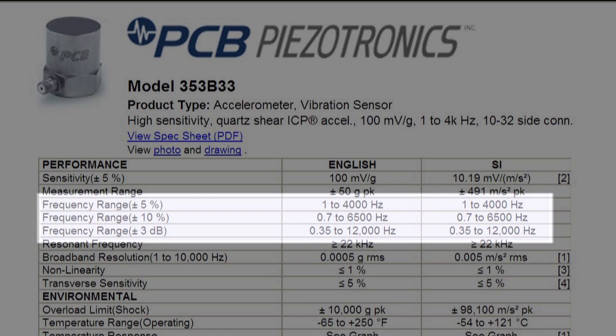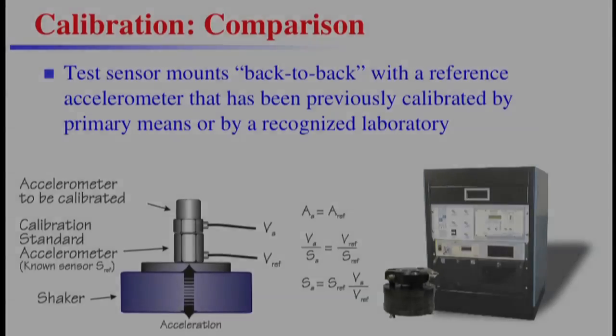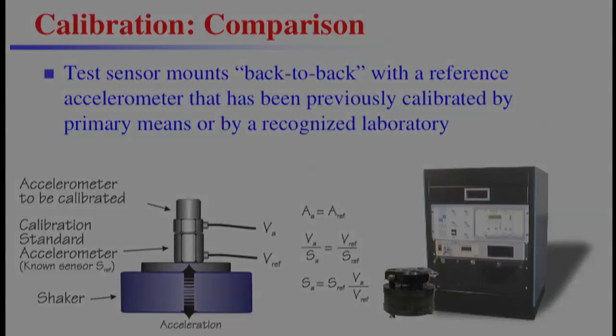The measured amplitude frequency response of a sensor is typically scaled in percent from the reference sensitivity. The comparison or back-to-back method is performed by mounting the sensor under test directly to the surface of the reference standard, which has a calibration traceable to one of the national labs. The fundamental assumption made is that the acceleration of the reference accelerometer and the acceleration of the sensor under test is equal.